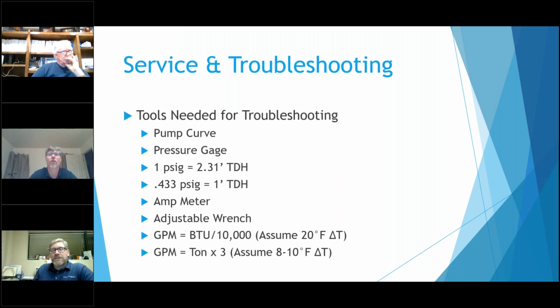There is an online selection software system where you can actually put the flow and head in, and it will generate the actual impeller curve that you might have for some of the larger pumps. Again, we'll get into that in a little bit. You can put the flow and head that you have of the pump, and then make an adjustment to the impeller if you don't have the right impeller diameter that it picks for you. Of course, the PSI to foot of head conversion, because the pump curves are in feet of head and all the gauges are in PSI.